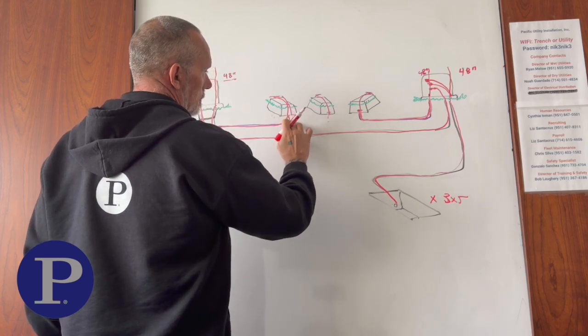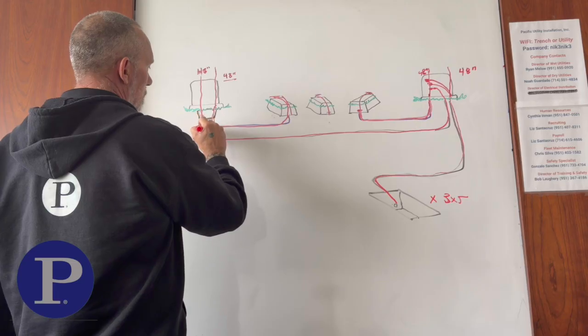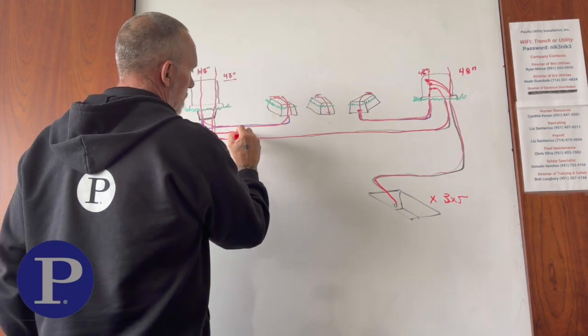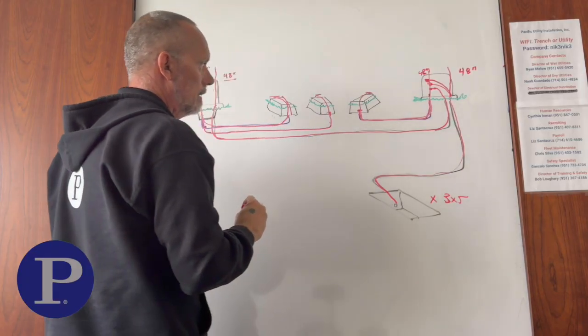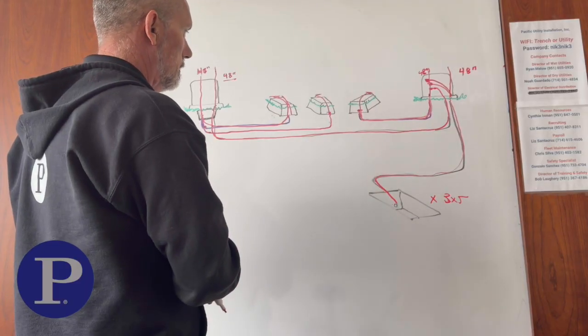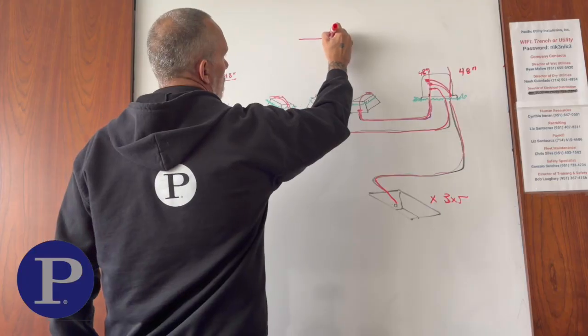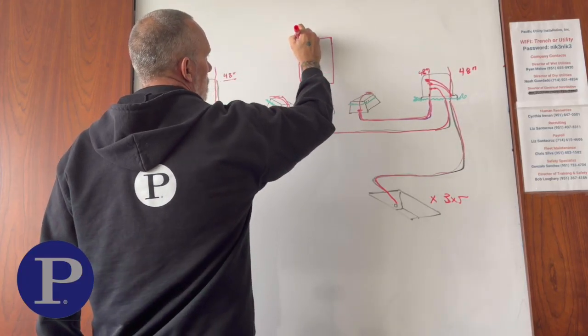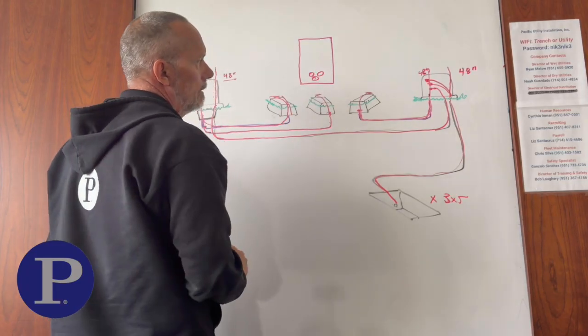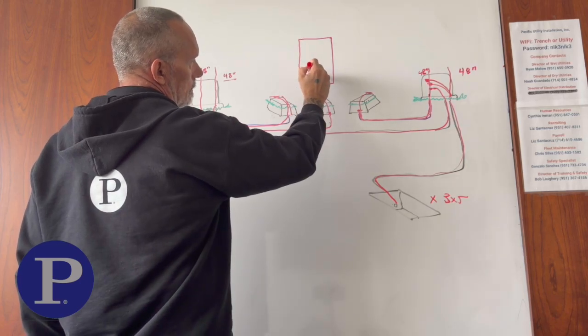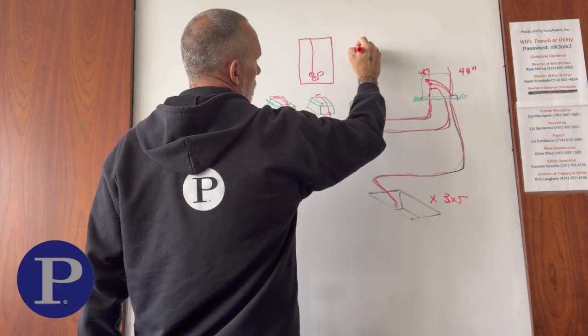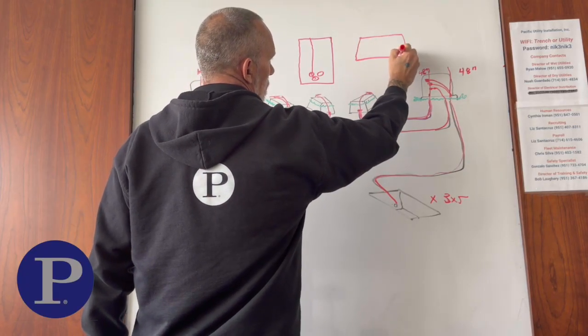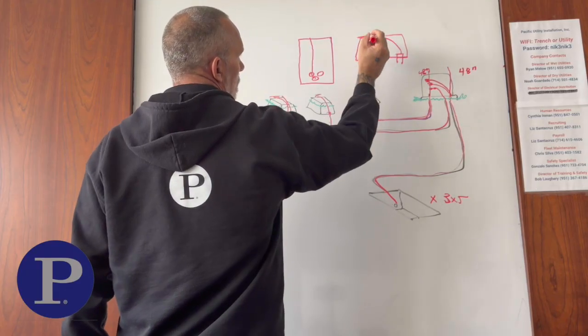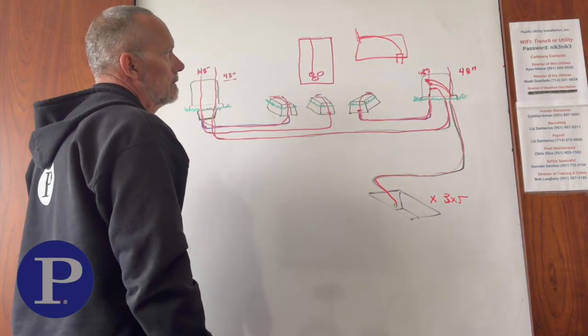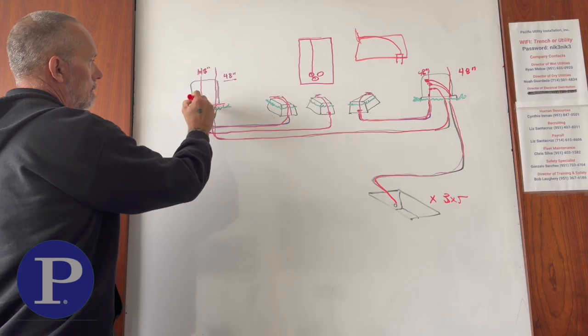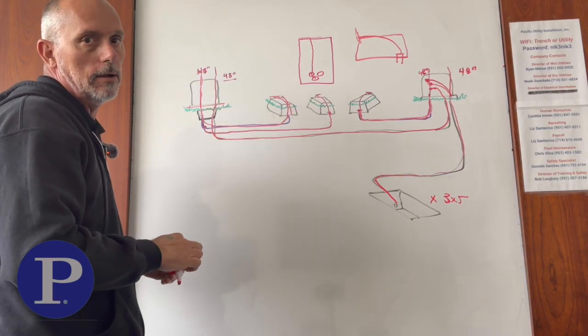Sometimes, instead of daisy chaining from handhole to handhole, it'll come from the transformer directly, bypass the first handhole into the second handhole. Those are just different ways that it could be set up. Again, looking at the top of the handhole, if your ducts are in here, if you're looking straight down at the handhole, you want your cable to come out and make a nice little loop. This is the side of the handhole, and your ducts are here. Make a nice little loop, cut it to the end of the handhole. Transformer pad, once again, approximately 42 to 48 inches above the top of the pad, that's where you're going to want to cut it.